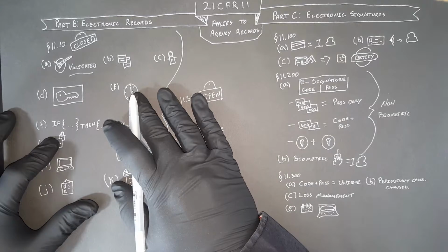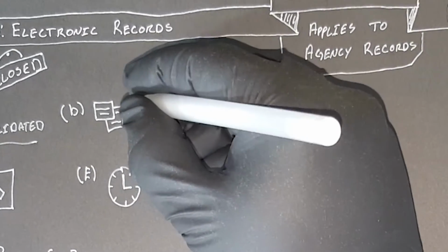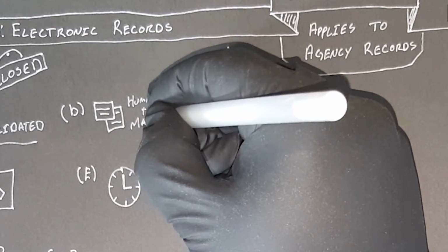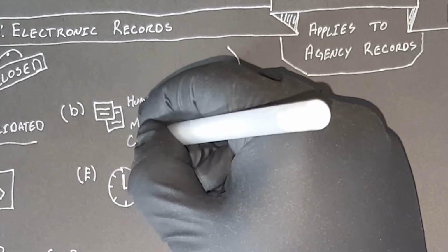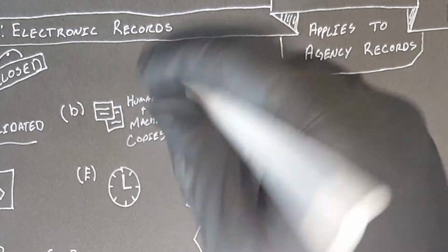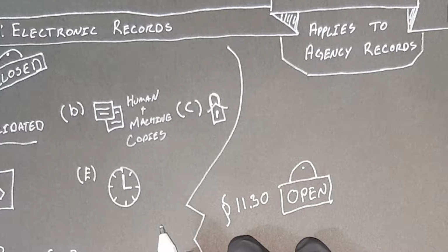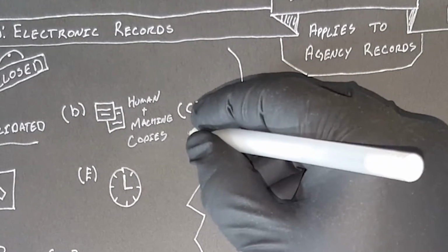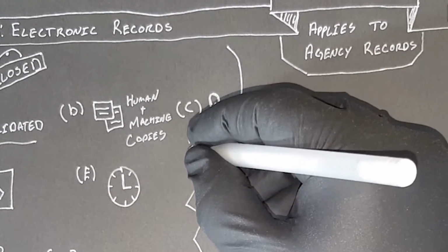So, moving on, the system must be able to create both human-readable and electronic formats. This needs to be for inspection if the agency comes in, and for review by people who may not have access to your closed system. So ultimately, you must be able to print something out of your system so that someone can read it. You have to have protection of your records, just as you would with any other doc control system, so that you're controlling and protecting these records throughout their retention period.